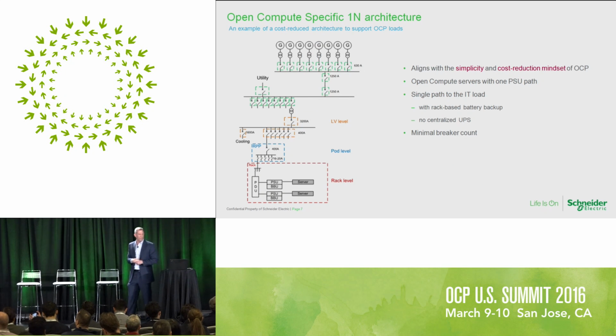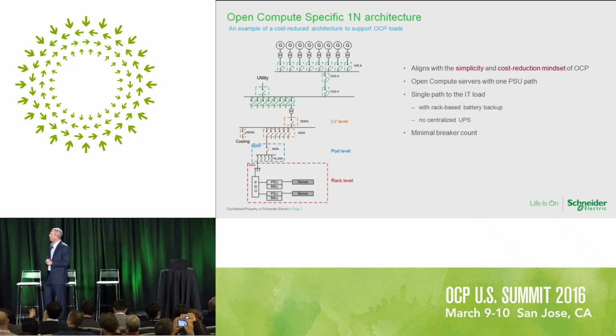If you compare it, this is what our one-line diagram looked like when we stripped out everything we possibly could. We kept generators, utility power coming in, one piece of switchgear at the LV level coming down to the pod, and then you have the power supply units and battery backup. So we eliminated the upstream UPS—everything is a power supply unit and a battery backup.